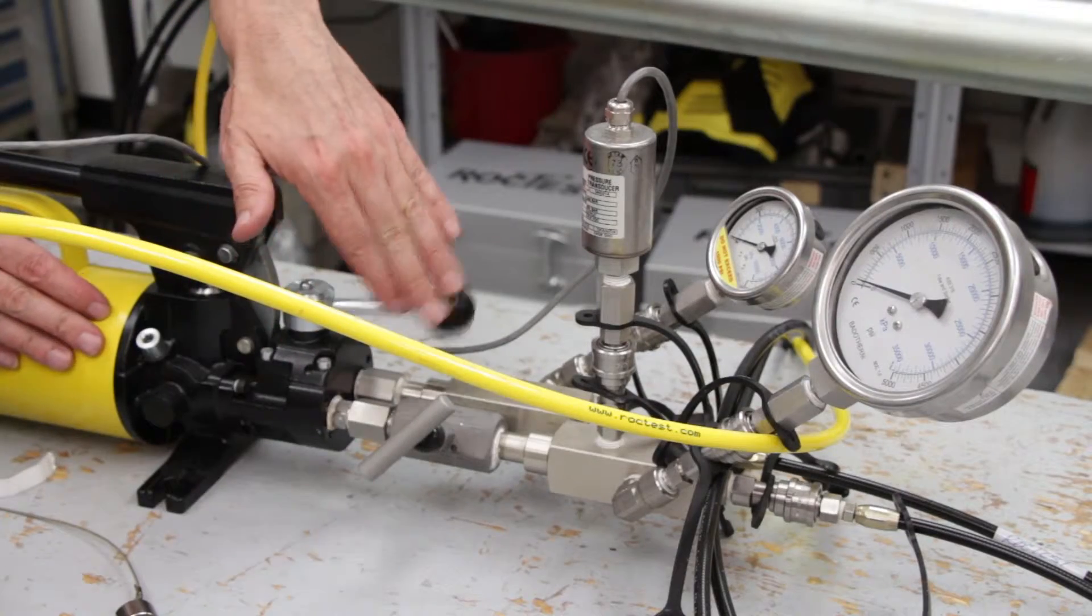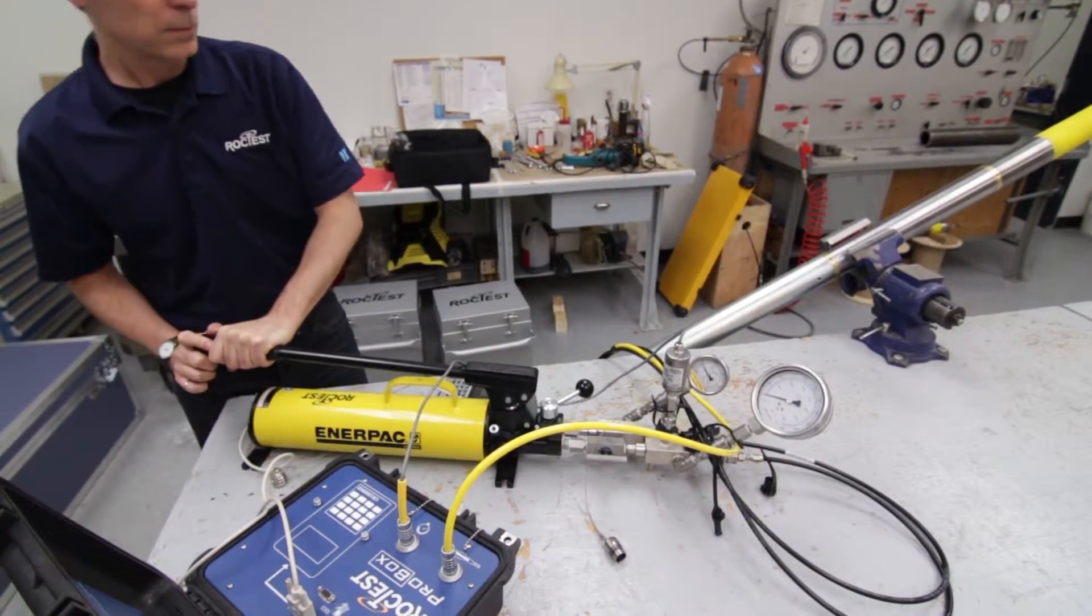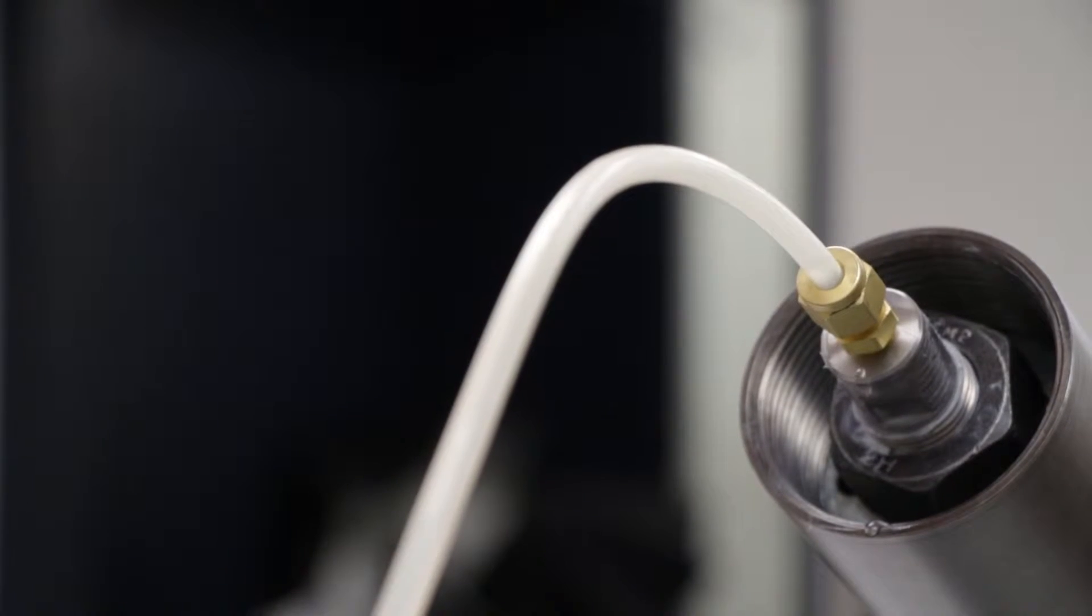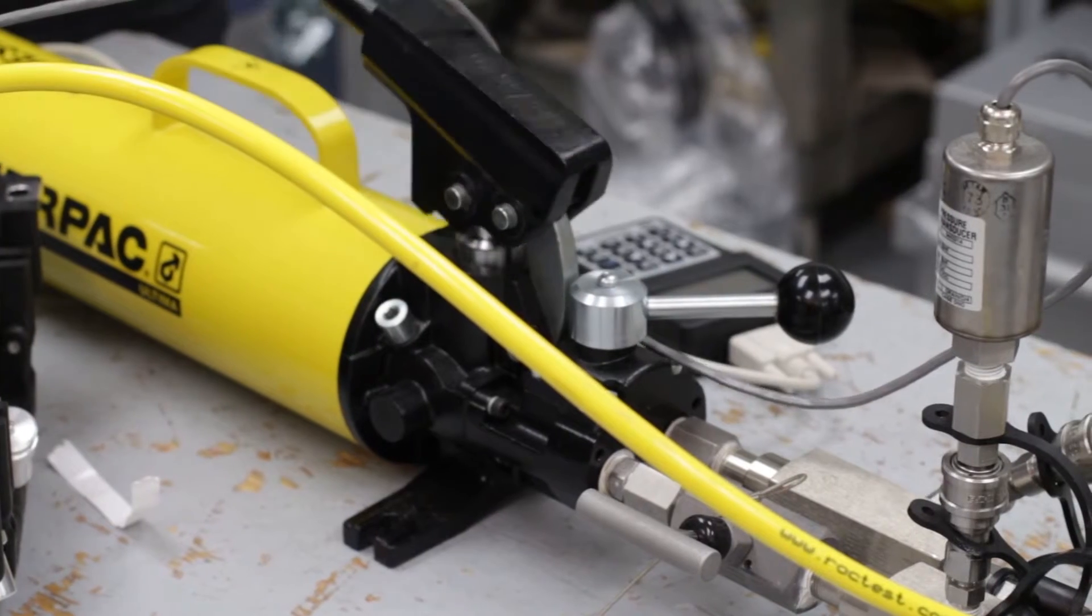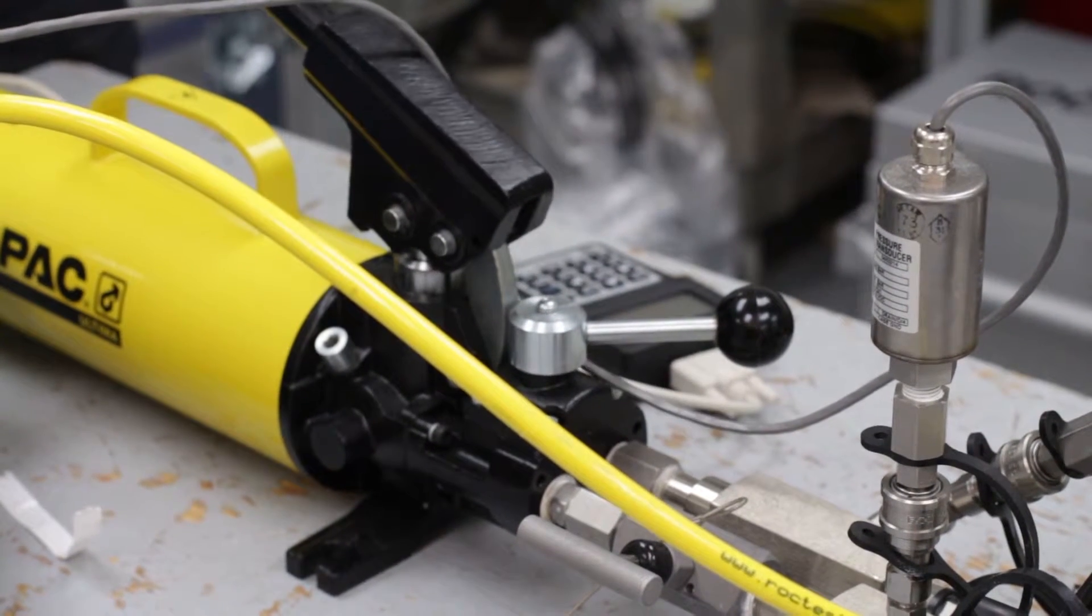Now place the pump's small handle on position 1 to activate the pump. If air is present in the probe, bubbles will be seen coming out of the tubing. Repeat the sucking in and expulsion of the water out of the probe until no air bubbles are expelled.